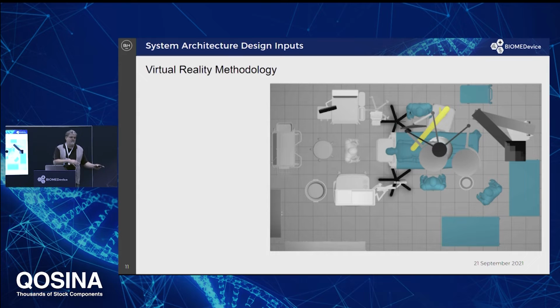I'll kind of demonstrate, actually, Bartosz is going to demonstrate later why you can't do that, because there's a surgeon in a cockpit over here, a controlling cockpit that controls the robot, and they need to be able to see the sterile field. Now you learn those kind of details from doing the contextual inquiry up front, what those needs are in a big picture. And here we're evaluating more minutia in the design iterations and configurations. So you might have 3 or 4 different versions of this robot, try them each out to see whether you can solve any of those problems. What you first thought was a big advantage, a really small footprint, it's only 2 feet by 2 feet, doesn't seem to make a difference as far as keeping that clinician on that side of the bed.